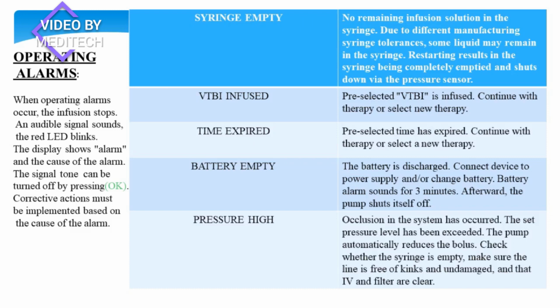Battery empty. The battery is discharged. Connect the device to a power supply and or change the battery. Battery alarm sounds for 3 minutes. Afterward, the pump shuts itself off. Pressure high. Occlusion in the system has occurred. The set pressure level has been exceeded. The pump automatically reduces the bolus. Check whether the syringe is empty. Make sure the line is free of kinks and undamaged, and that IV and filter are cleared.